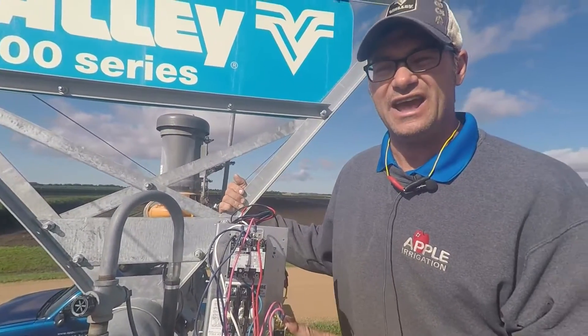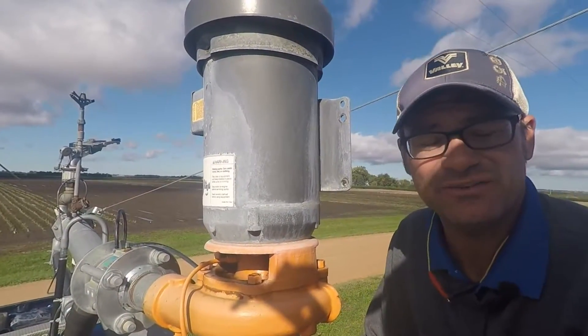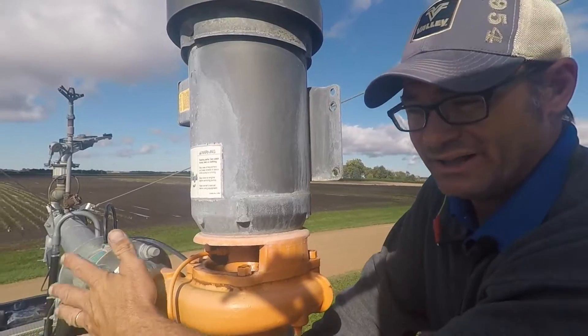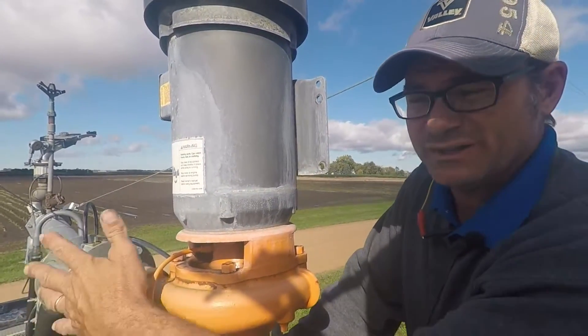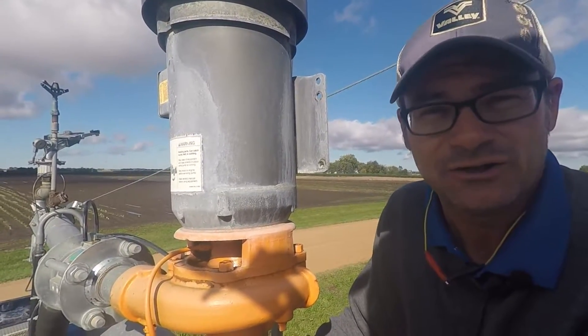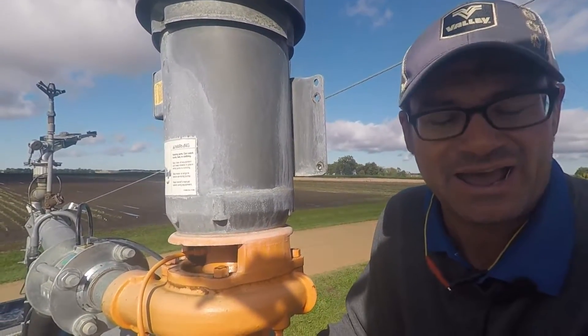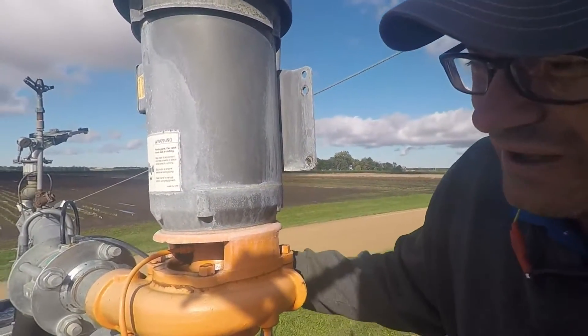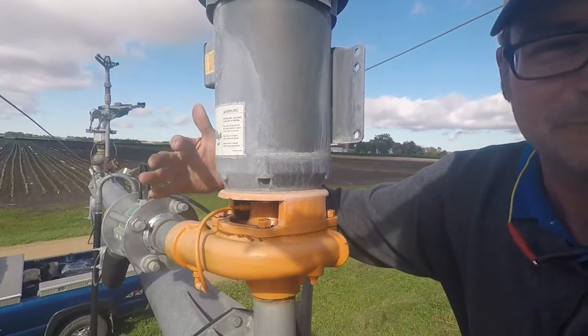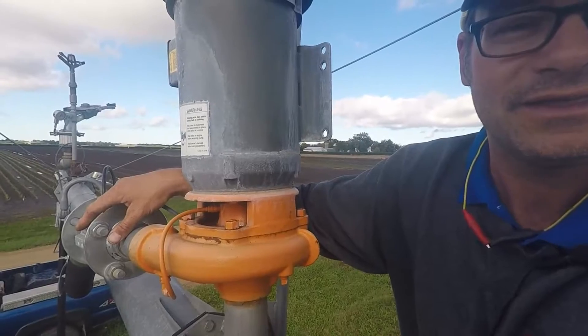We're on top of an irrigator with a five horsepower booster pump and a Nelson 800 series valve. If you purchase your Valley irrigator from Apple Irrigation and it has a booster pump, it's going to have this Nelson 800 series valve. We put this on every irrigator we sell automatically because we found that it really eliminates a lot of issues with the end gun not coming on. Using this valve we eliminate the electric solenoid and it really improves the reliability of the machine. All this valve does is it senses a difference in pressure — line pressure versus boosted pressure. When it sees that difference, the valve automatically opens and the water flows out of the end gun.